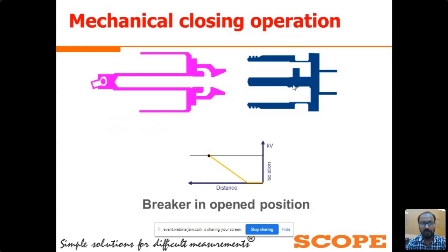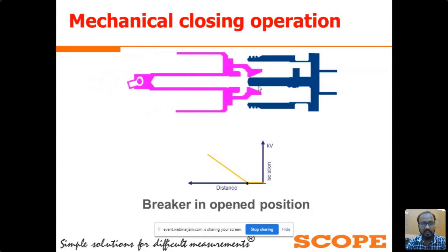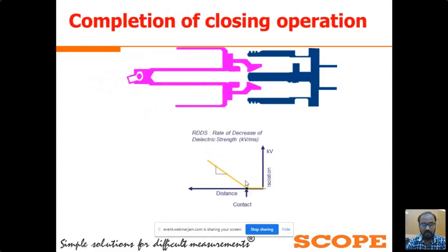Here we can see this is a fixed contact of the circuit breaker, and this is a moving contact of the circuit breaker. In the graph, you can see the distance between these CB contacts and the dielectric strength between the circuit breaker contacts. On this vertical line is the dielectric strength, which is the isolation voltage between the circuit breaker contacts, and this is the distance between the CB contacts. With reducing distance between the CB contacts, the dielectric strength between the CB contacts is getting reduced. This is called the rate of decrease of dielectric strength.